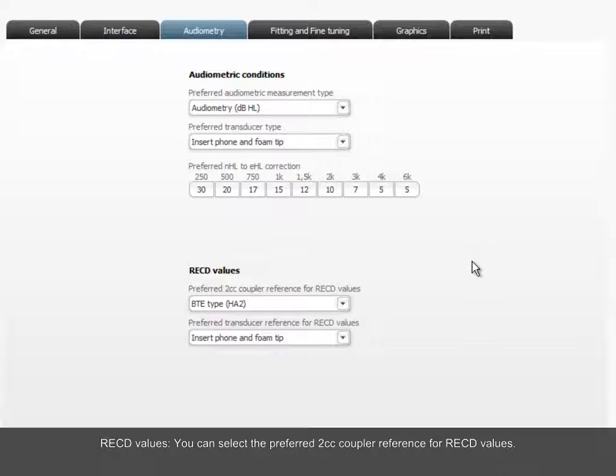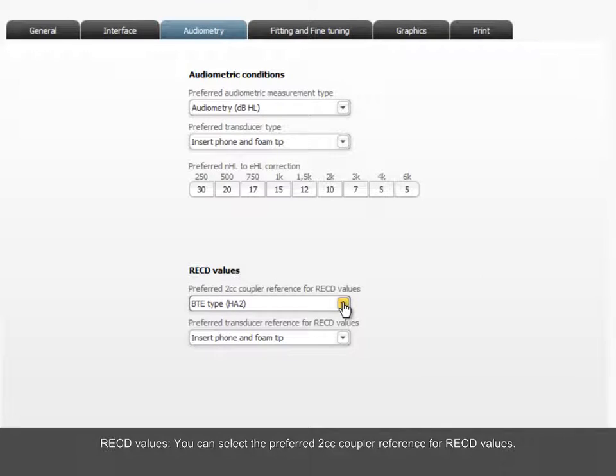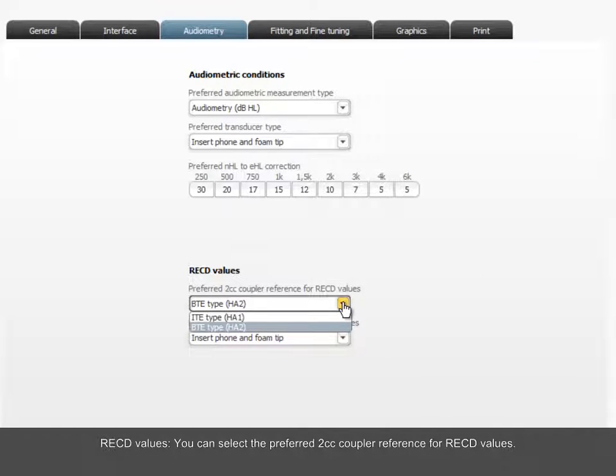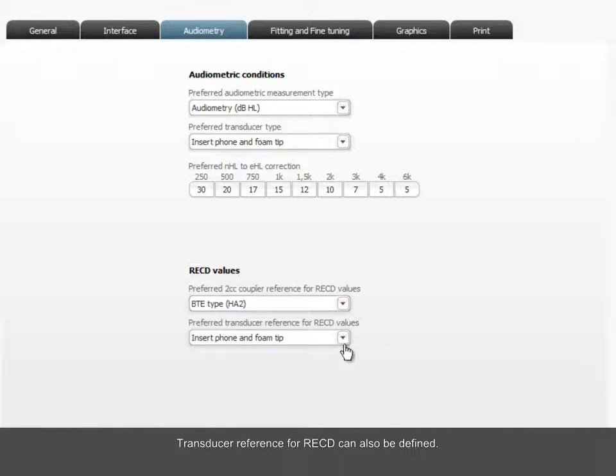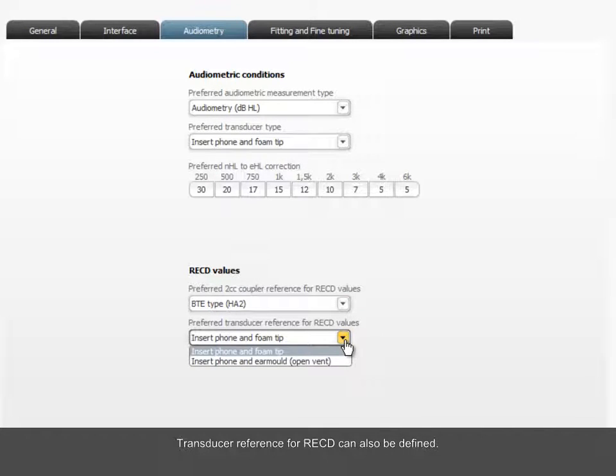You can select the preferred 2cc coupler reference for RECD values. Transducer reference for RECD can also be defined.